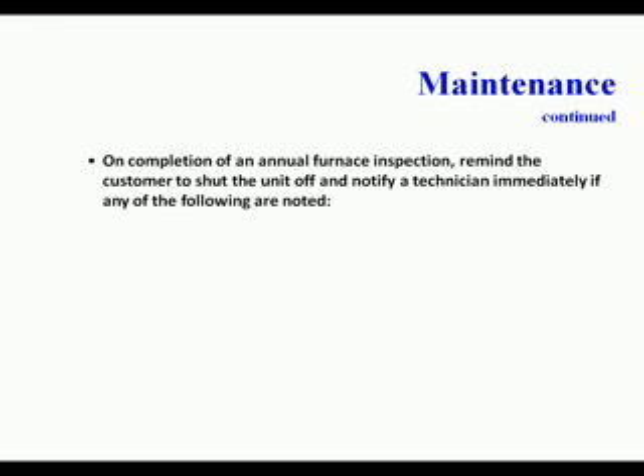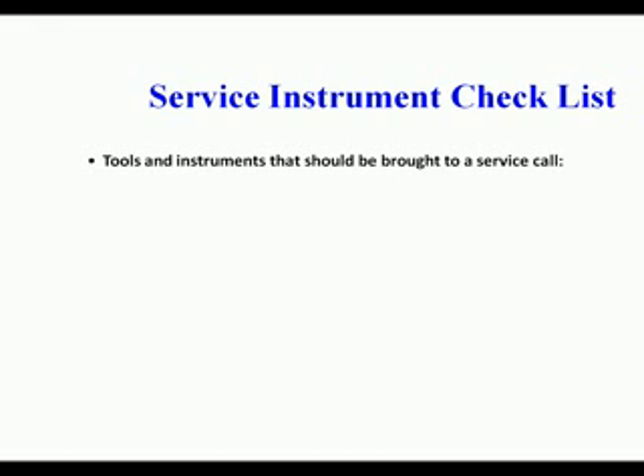With the system running and operating, check the performance of the unit and vent system. The flue product should be analyzed and compared to the unit specifications. Upon completion of any furnace inspection, remind the customer to shut the unit off and notify a service company or technician immediately if any of the following are noted: new and unfamiliar sounds while the unit is operating, any unusual odors, unusual amounts of moisture in the heated space, visibly burned components, or unusual dirt or rust accumulation of the vent pipe or unit. If any flu-like symptoms subside when inhabitants are away from the house, this may indicate carbon monoxide poisoning.